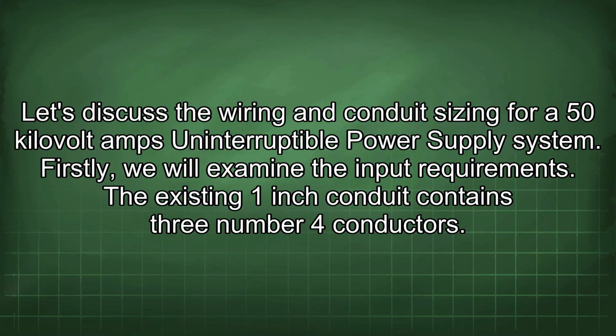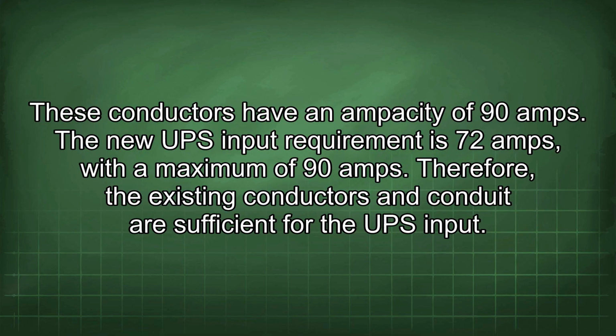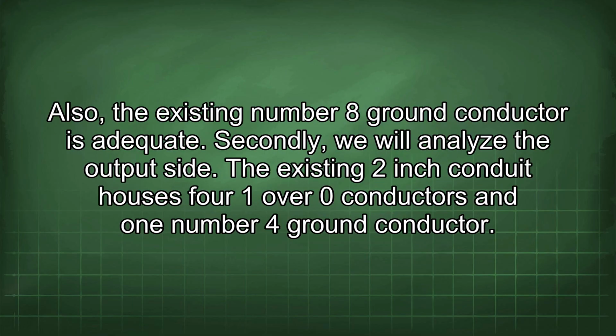Let's discuss the wiring and conduit sizing for a 50 kVA uninterruptible power supply system. Firstly, we will examine the input requirements. The existing 1-inch conduit contains 3 number 4 conductors. These conductors have an ampacity of 90 amps. The new UPS input requirement is 72 amps, with a maximum of 90 amps. Therefore, the existing conductors and conduit are sufficient for the UPS input. Also, the existing number 8 ground conductor is adequate.